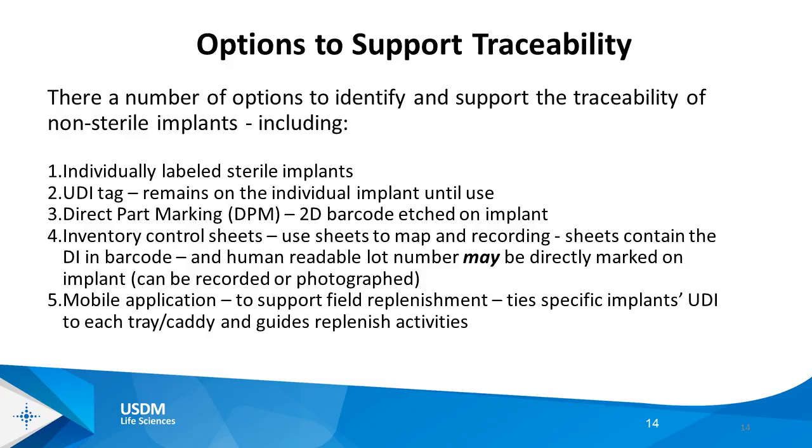You didn't want direct marking, and that's fine. And I think the comments, by far the most organized and persuasive comments that were received on the proposed rule, were around the cost and complexity of direct marking. So that requirement is gone, but we're left with this gap that I don't think we all particularly understood at the time, in terms of how we identify a device at the point of implantation, which always was the point, the key, the focus and driving factor for UDI around these device types. There are obviously a number of other activities for different devices, but this was really the key.